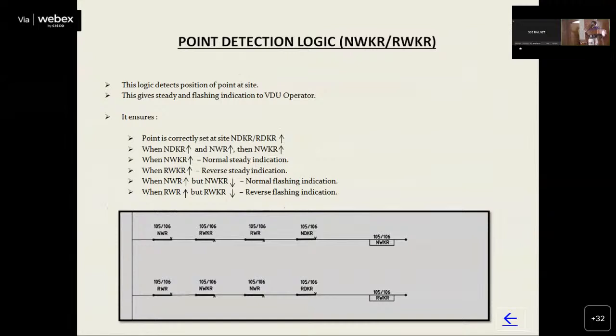Point detection logic, NWKR and RWKR. This logic detects the position of the point at site. This gives steady and flashing indication to the VDU operator. Like when the point is correctly set, NDKR, RDKR is up. When NDKR is up and NWR is up, then NWKR is up. These are the conditions for the point to be in flashing condition or in a steady condition.